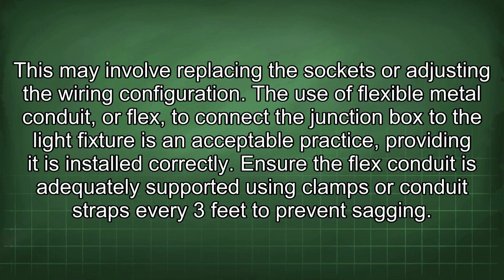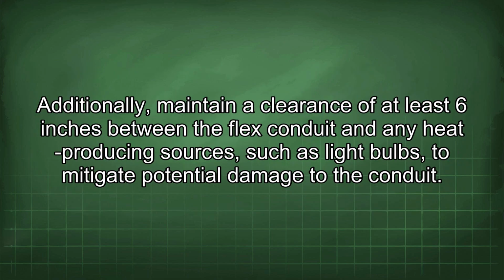The use of flexible metal conduit, or flex, to connect the junction box to the light fixture is an acceptable practice, providing it is installed correctly. Ensure the flex conduit is adequately supported using clamps or conduit straps every 3 feet to prevent sagging. Additionally, maintain a clearance of at least 6 inches between the flex conduit and any heat-producing sources such as light bulbs to mitigate potential damage to the conduit.